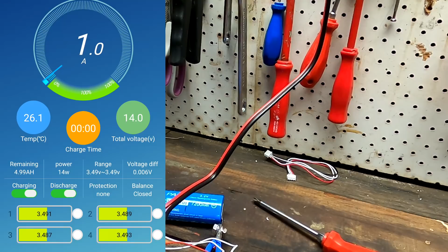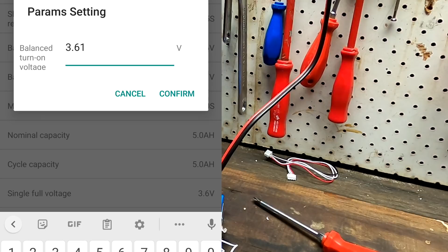3.45 we had set before as the maximum cell voltage, and this is already in the steep part of the curve. And now we have hit 3.6 volts here already. I need to set the balancer differently. Here, we can set this now to 3.61, for example. Yeah, 3.6 is our cell voltage under optimal conditions, and 3.61 would be our balance voltage. Confirm, then we go back.